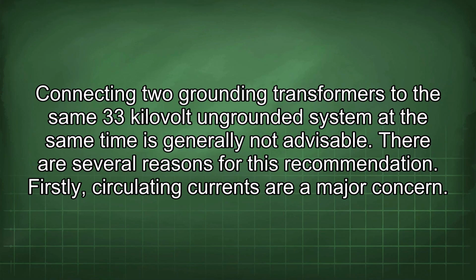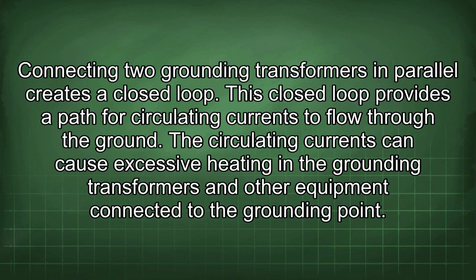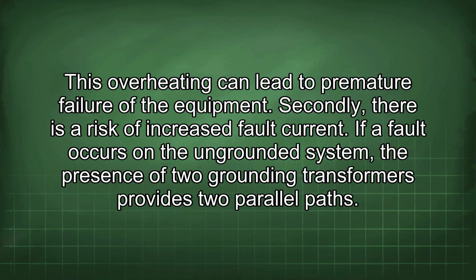Connecting two grounding transformers to the same 33 kV ungrounded system at the same time is generally not advisable. There are several reasons for this recommendation. Firstly, circulating currents are a major concern. Connecting two grounding transformers in parallel creates a closed loop. This closed loop provides a path for circulating currents to flow through the ground. The circulating currents can cause excessive heating in the grounding transformers and other equipment connected to the grounding point. This overheating can lead to premature failure of the equipment.